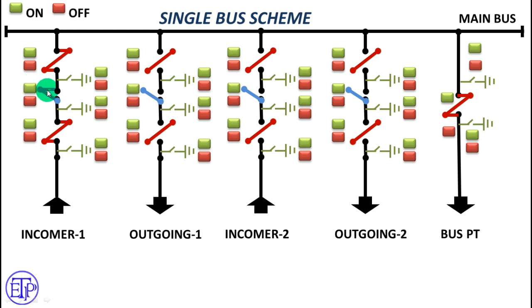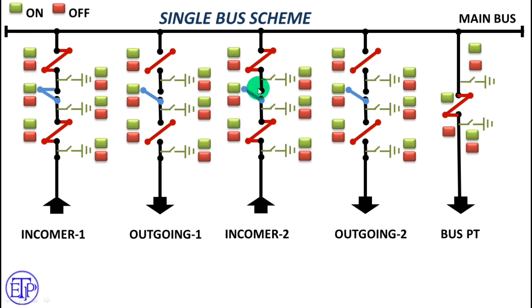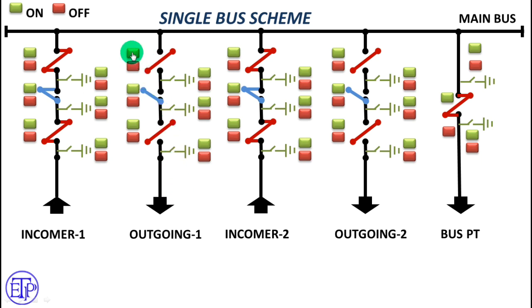Now we can charge the second incomer also. For this case, we will first close this isolator, then this isolator — or we can do it in reverse order. Before closing this breaker, we have to match the synchronization, because the first incomer is already giving power to this bus bar. This power source should be in sync with the other power source — by checking that, we can close this breaker also. Now two incomers are closed. For the closing of the outgoing feeder, we will first close the two isolators and then close the circuit breaker.